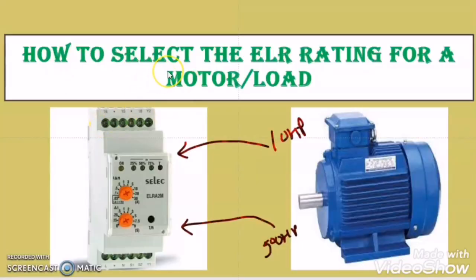So our question is still valid: how to select the ELR rating for a particular motor or a particular load, as the ELR and the CBCT are not depending on the load current in healthy condition as well as in the faulty, earth fault condition. It completely depends on how much protection you need from the earth leakage. Suppose you want to trip your circuit at 1 ampere leakage current, then you have to select an ELR which has a range till 1 ampere or above, so that you have the option to select 1 ampere. If you want the system to trip when there is an earth leakage current of 30 milliampere, then select an ELR which has a setting down to a minimum of 0.03 ampere or 30 milliampere. And how fast you need the circuit breaker to trip, in that way you have to select the range of the ELR on a time basis. This is the general thing.